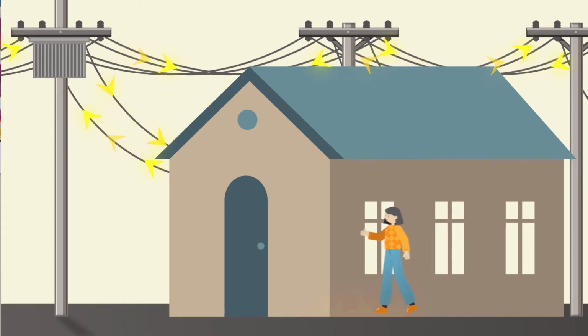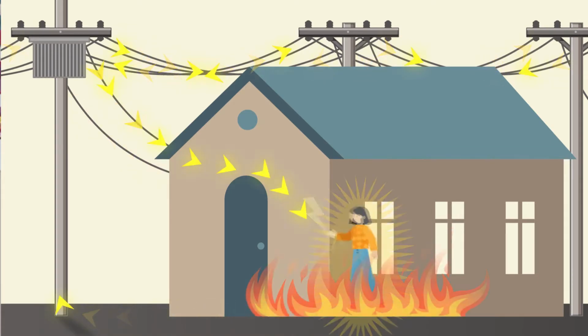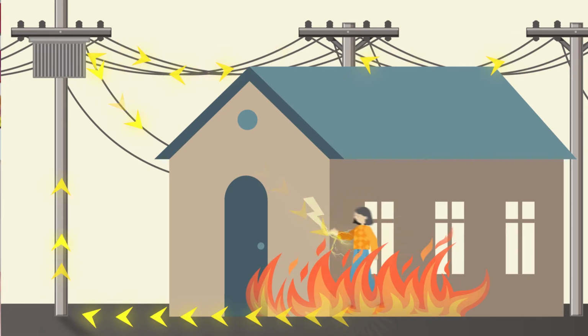You might be wondering, why is the earth a perfectly fine return path for the current? Shouldn't that be the neutral? As it turns out, the way the electric grid is built in most countries, the neutral and the earth are connected together at the transformer level.